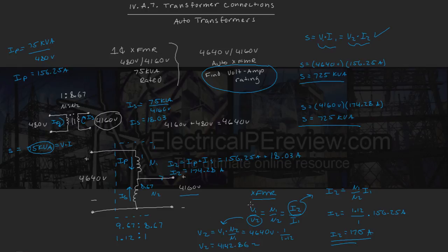Next, let's try solving for V1 using just our currents. So V1 is equal to I2 over I1 times V2. So this comes out to I2, our output autotransformer current that we found to be 174.28 amps, divided by our input current, which was the same as our primary winding current, which we found to be 156.25 amps. We times it by our output voltage on our autotransformer, which is 4160. We should come real close to our input 4640 volts. We run the numbers and we come up with an exact 4640 volts. So all the math checks out.